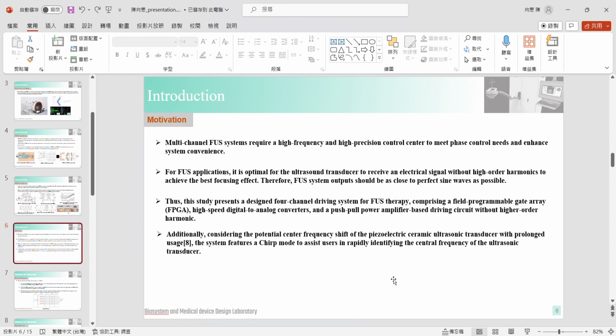Our motivation is that multi-channel FUS systems require a high frequency and higher precision control center to meet phase control needs and enhance system convenience. For FUS applications, it is optimal for the ultrasound transducer to receive an electrical signal without high order harmonics to achieve the best focusing effects. Therefore, the FUS system output should be as close to a perfect sine wave as possible.